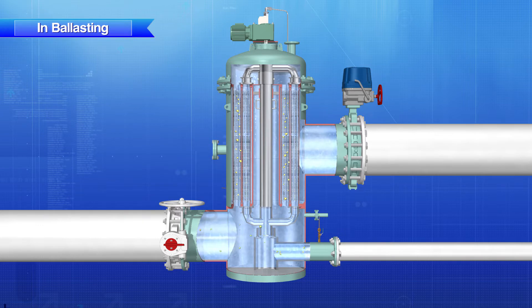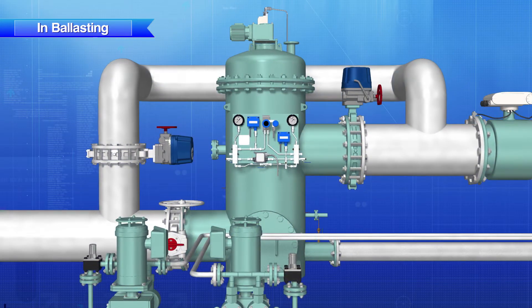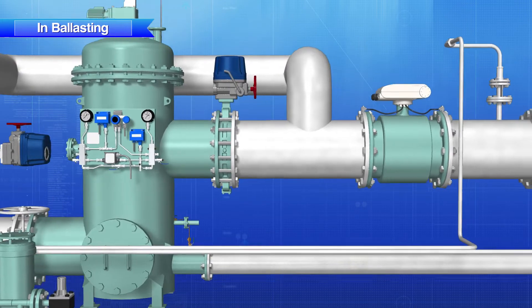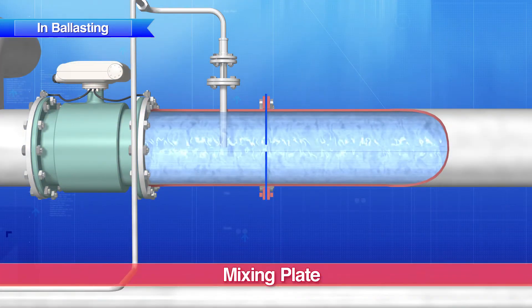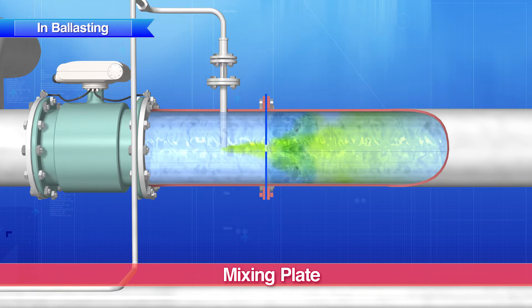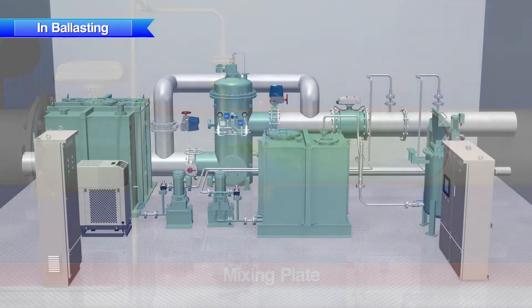The filter elements are automatically backwashed in rotation to prevent clogging. At the same time, other filter elements continue the treatment process. Next, the disinfectant is injected into the ballast water through the injector and the remaining microorganisms and bacteria are sterilized. Once the disinfectant has been injected, the ballast water is stirred by a mixing plate specifically designed by JFE in order to mix the disinfectant homogeneously.